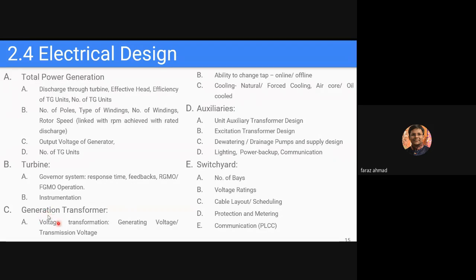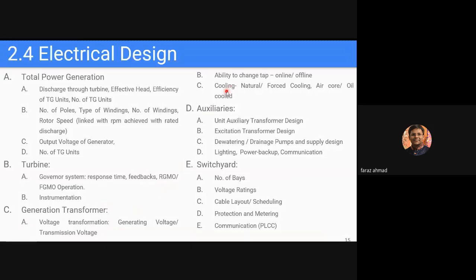Then there is the generating transformer. As I told you, lower voltage generation is done to save on insulation and the dimension of the machine, so you generate at low voltage and high current. You need to design the generating and transmission voltages, and the transformer sets up the voltage, with certain restrictions by the Indian Standard Code. Then there is the ability to change tap offline or online, these are features provided in the transformer.